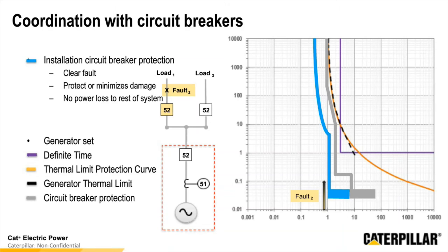So in this case, the blue curve is now representing a feeder breaker down into the system, feeding our load 1 in this instance, which would say roughly about 20% of the rated would be supported continuously. And then we have a curve that's allowing some additional power for different reasons. So in this case, if we were to experience a fault that is just under the 100% rated for the package, we would clear the fault at roughly 5 seconds, and that would be the breaker, the 52 device shown further down into the system. If we had that same amount of power and for some reason that 52 device did not trip, then we would go all the way up to just over 100 seconds before the generator breaker would recognize that fault and see that as a failure and trip the system. So we want to make sure we're coordinating to allow enough current to the system to support loads as necessary, but we're also coordinating these breakers such that we're protecting the system overall.